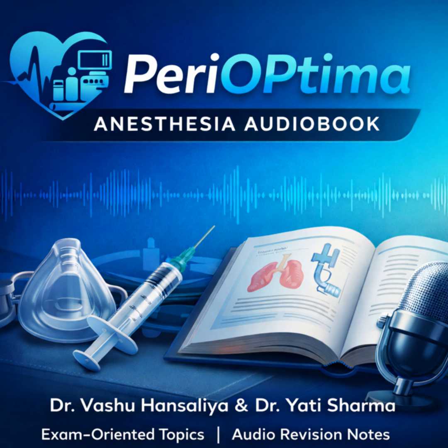And what about position 4, the R? That's for rate modulation. A device with an R in its code, like VVIR or DDDR, has a sensor inside. It could be an accelerometer that detects motion, or a sensor that measures thoracic impedance to estimate minute ventilation. So it knows when you're exercising. It knows when your metabolic demand is up, and it increases the pacing rate accordingly. It restores that chronotropic competence we talked about. That's a great breakdown. Let's move to Part D, function and features.